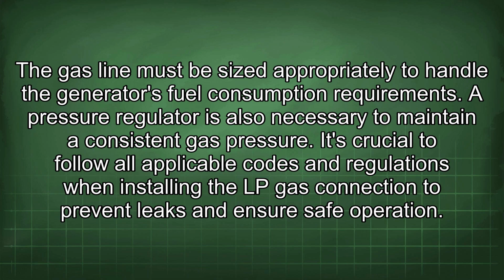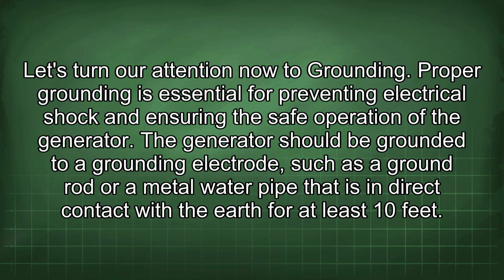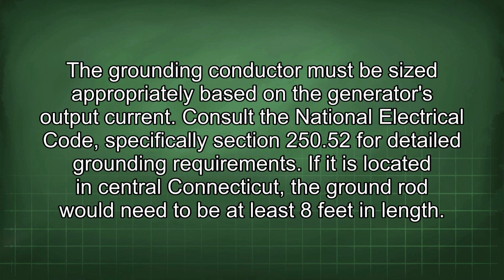Let's turn our attention now to grounding. Proper grounding is essential for preventing electrical shock and ensuring the safe operation of the generator. The generator should be grounded to a grounding electrode, such as a ground rod or a metal water pipe that is in direct contact with the earth for at least 10 feet. The grounding conductor must be sized appropriately based on the generator's output current. Consult the National Electrical Code, specifically Section 250.52, for detailed grounding requirements. If located in central Connecticut, the ground rod would need to be at least 8 feet in length.